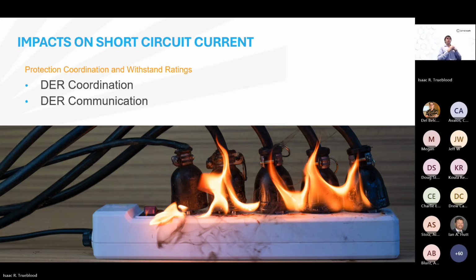And you might be asking, what about unstable islanding? That sounds pretty dangerous, right? And that is true. An unstable island is incredibly dangerous. However, this can also be mitigated. Having distributed energy resources and the protective equipment communicate with other feeder protective equipment will ensure the distributed energy resources protection knows when an upstream protection device is tripping offline, regardless of if the distributed energy resources protective equipment can detect the fault condition. This ensures that the distributed energy resources does not create an unstable island.